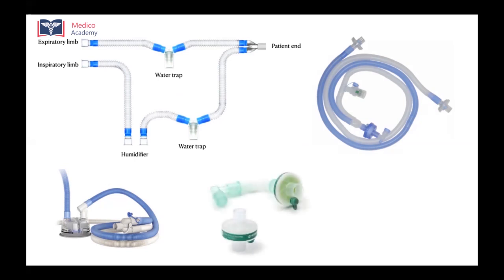So this is a bacteria filter cum HME, or the heat and moisture exchanger. So it has both purposes. It acts as a bacteria filter as well as it acts as an HME. And this is usually connected to the patient end of the circuit. So this is a nebulization kit, a nebulizer with a TPS connection and an oxygen tubing. So this is also another connection which usually comes in the ventilator circuit.